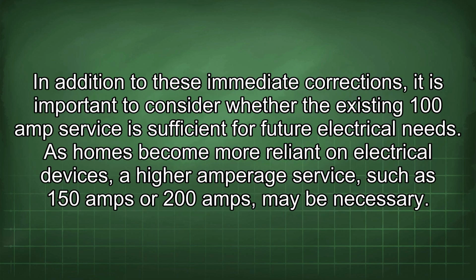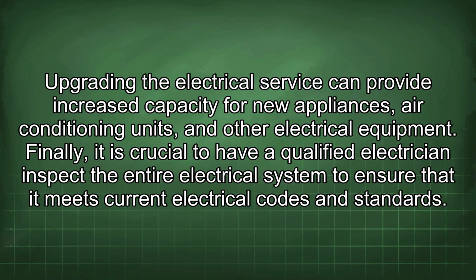In addition to these immediate corrections, it is important to consider whether the existing 100 amp service is sufficient for future electrical needs. As homes become more reliant on electrical devices, a higher amperage service, such as 150 amps or 200 amps, may be necessary. Upgrading the electrical service can provide increased capacity for new appliances, air conditioning units, and other electrical equipment.